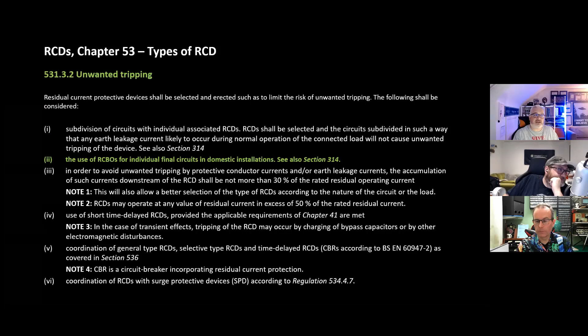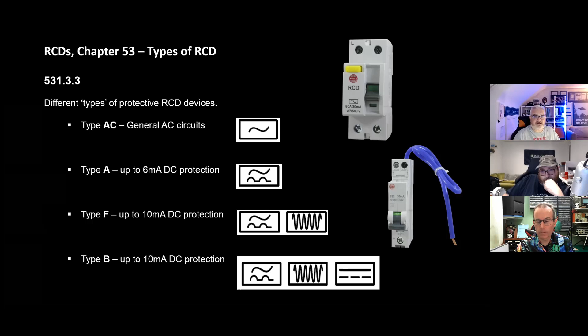For anyone who is a learner or on that journey, just a quick reminder of the different types of RCDs. When we say types, we don't mean MCBs. Type AC is for general resistive loads. Type A provides up to 6 milliamp of DC protection, which is really not much. Type F is up to 10 milliamp with protection against high frequency loads. Type B is all types of DC, whether constant, chopped, inverted, rectified, etc., plus high frequency loads. When you go type F and B, it gets very expensive. As I said yesterday, there was a guy who had a coffee machine on a dedicated circuit, lots of money.